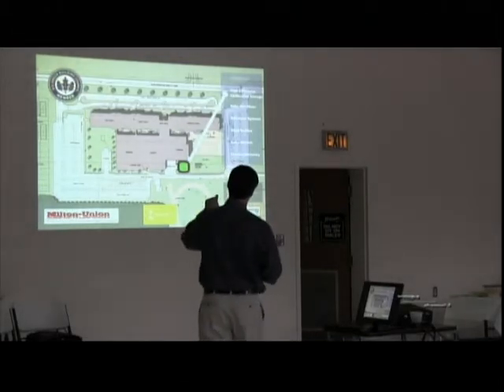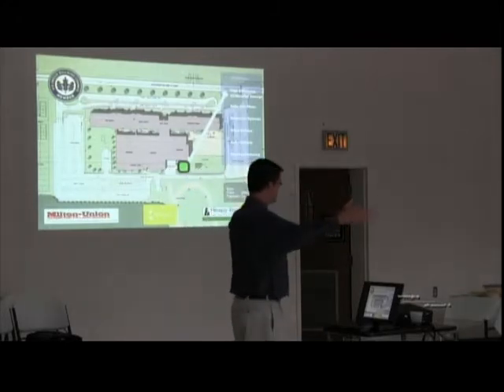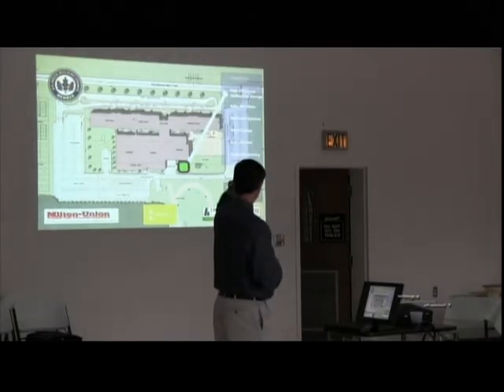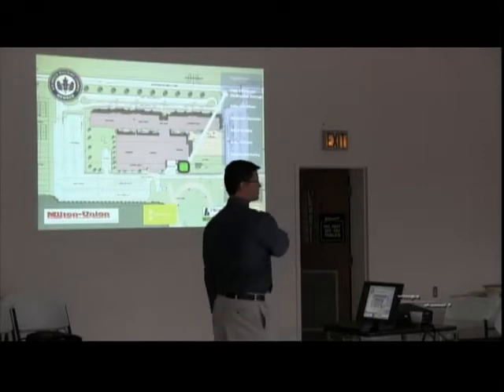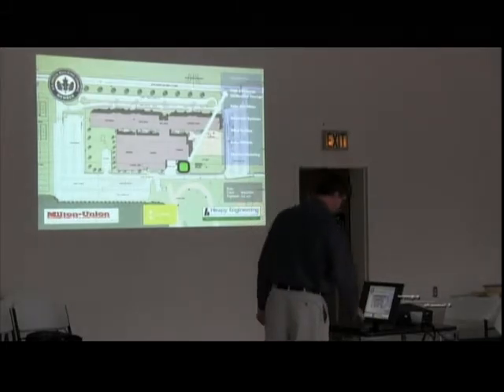Another thing we're doing with those chillers is we've got ice storage. So we are making ice during the night when electricity rates are lower, and then during the day we are circulating a water glycol solution through these. There are like 12 of them. They're about 8 feet in diameter and about 10 feet tall containers that are back in that chiller yard that's highlighted on the slide. And those are filled with ice. Basically, ice is made during the night, and then we use that ice to cool the building during the day. So you're actually taking advantage of a lower rate to cool the building.